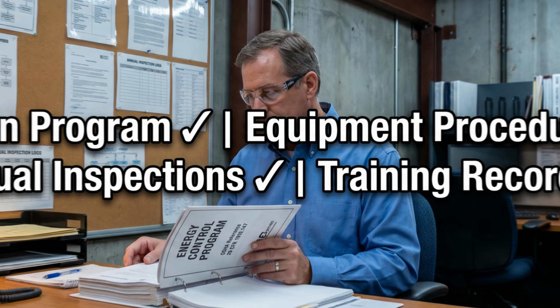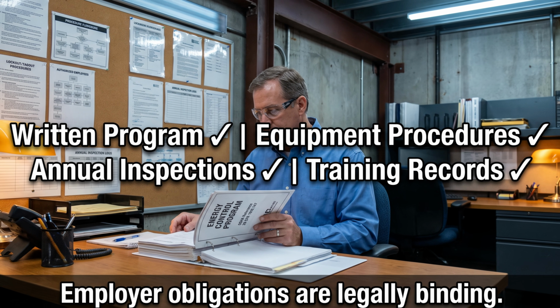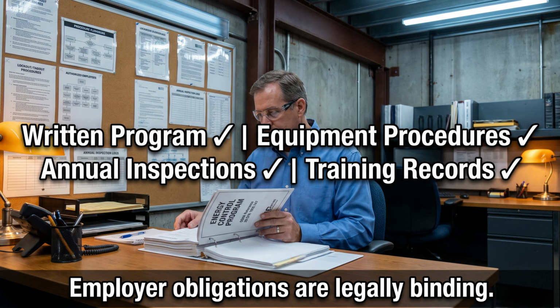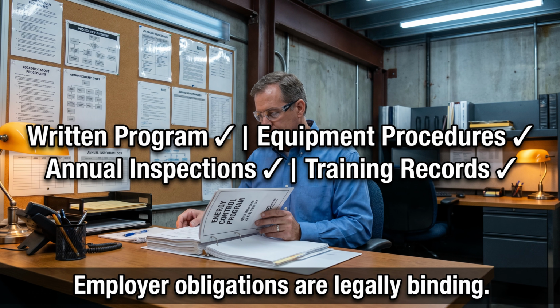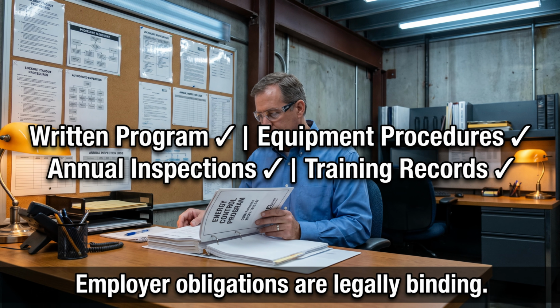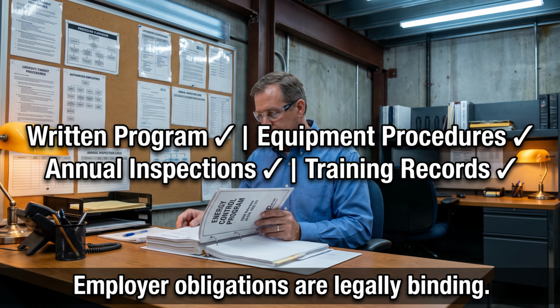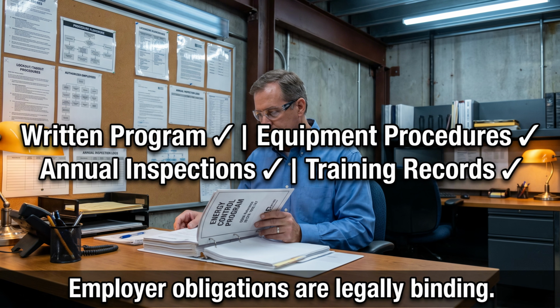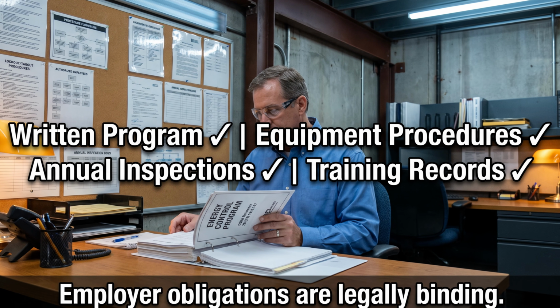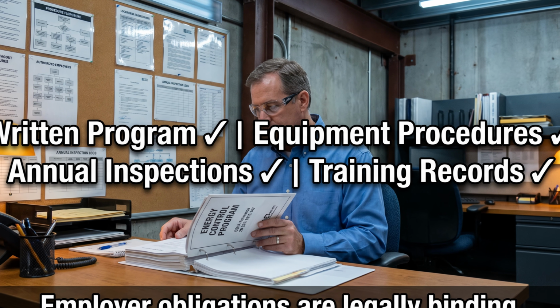Only the person who applied it can remove it. Your employer has obligations too. They must develop a written energy control program, create specific written procedures for each piece of equipment with multiple or complex energy sources, provide training and retraining when necessary, and conduct periodic inspections, at least annually, of every energy control procedure. Your facility's Lockout Tagout program is only as good as its written foundation.